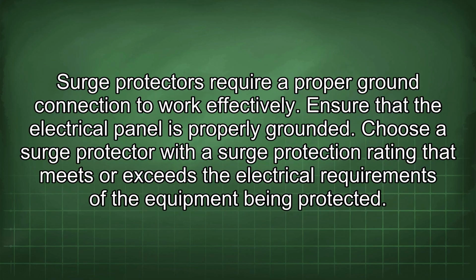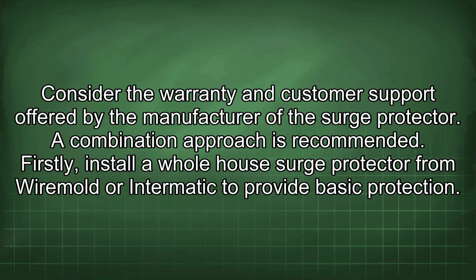Surge protectors require a proper ground connection to work effectively. Ensure that the electrical panel is properly grounded. Choose a surge protector with a surge protection rating that meets or exceeds the electrical requirements of the equipment being protected. Consider the warranty and customer support offered by the manufacturer of the surge protector.